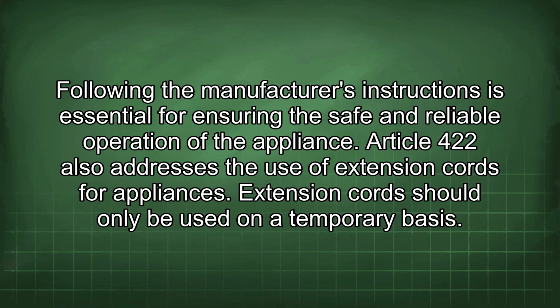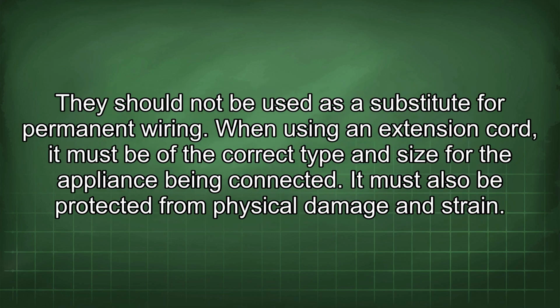Article 422 also addresses the use of extension cords for appliances. Extension cords should only be used on a temporary basis. They should not be used as a substitute for permanent wiring. When using an extension cord, it must be of the correct type and size for the appliance being connected. It must also be protected from physical damage and strain.